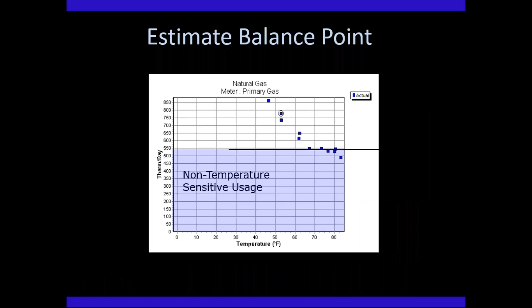Here's the same thing with gas. I go through the same exercise, imagining a horizontal line and another line slanting up to the left. Where these two intersect is my balance point. Here it's 67 degrees, the temperature at which the building starts to heat, meaning at any temperature below 67 we're in heating.